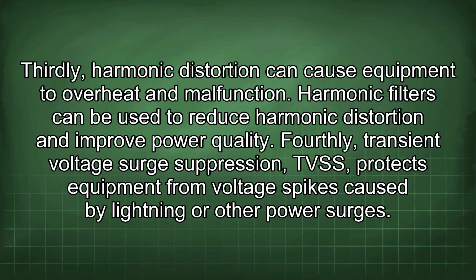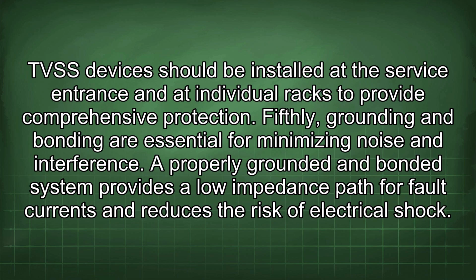Thirdly, harmonic distortion can cause equipment to overheat and malfunction. Harmonic filters can be used to reduce harmonic distortion and improve power quality. Fourthly, transient voltage surge suppression, TVSS, protects equipment from voltage spikes caused by lightning or other power surges. TVSS devices should be installed at the service entrance and at individual racks to provide comprehensive protection.